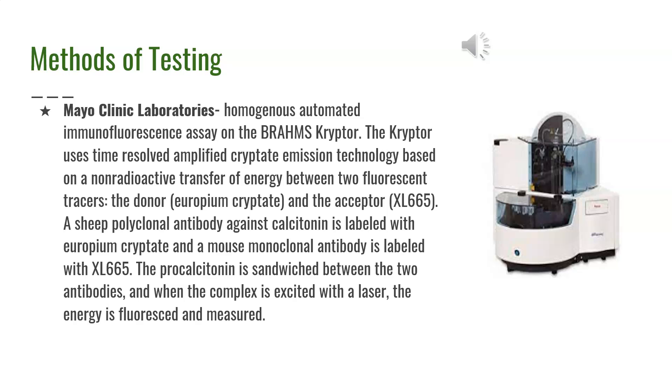There are many different methods of testing for procalcitonin, but this slide focuses on Mayo Clinic Laboratories. They use a homogeneous automated immunofluorescence assay on the BRAHMS KRYPTOR analyzer. The KRYPTOR uses time-resolved amplified cryptate emission technology based on a non-radioactive transfer of energy between two fluorescent tracers: the donor tracer europium cryptate and the acceptor tracer XL665. Procalcitonin is sandwiched between the two antibodies, and when the complex is excited with a laser, the energy is measured.